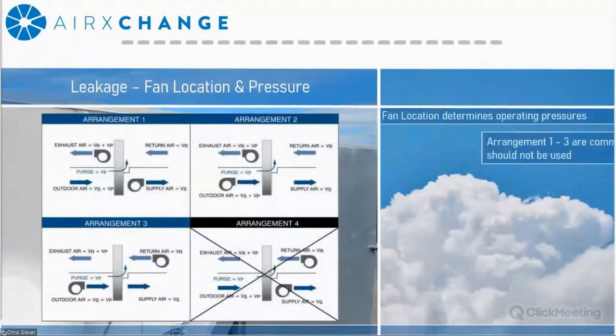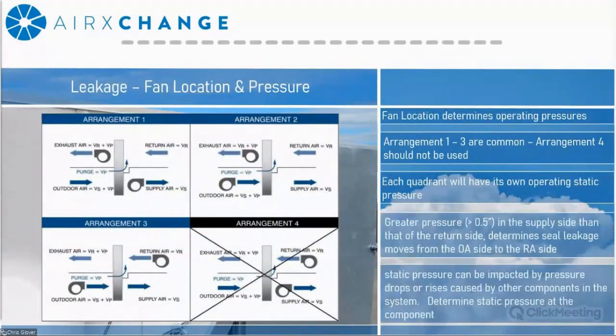So starting with fan location. Fan location is critical as it's going to determine the system's operating pressures. You're going to take note where they're located, and the inspection is going to require taking static operating pressures. The three most common fan arrangements are displayed in the image to the left. If you find that you have the fourth arrangement, you should contact the equipment manufacturer for advice on how to operate this, as these configurations are prone to excessive amounts of potential recirculation.